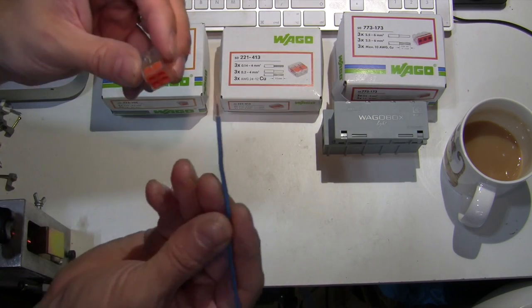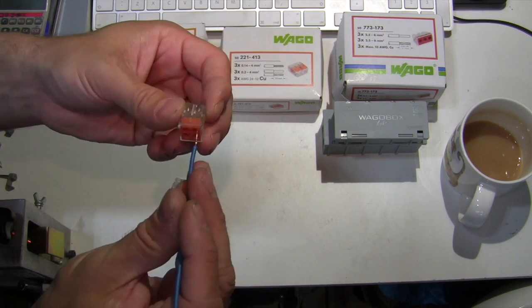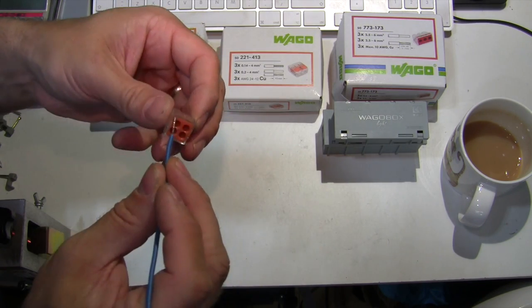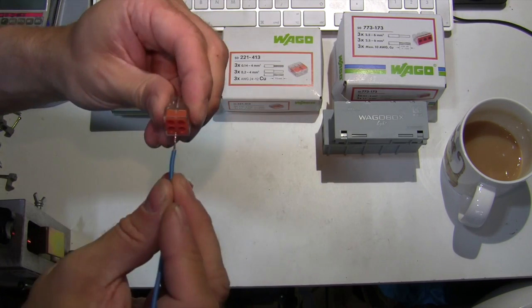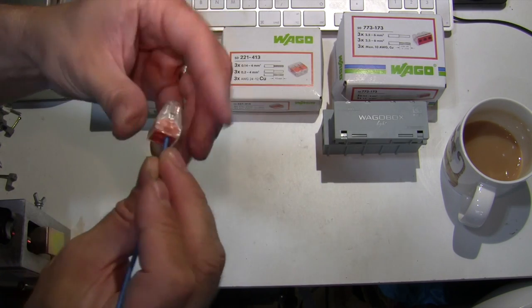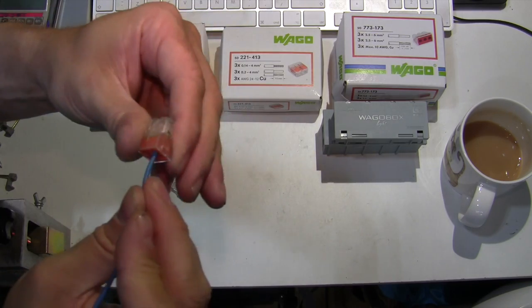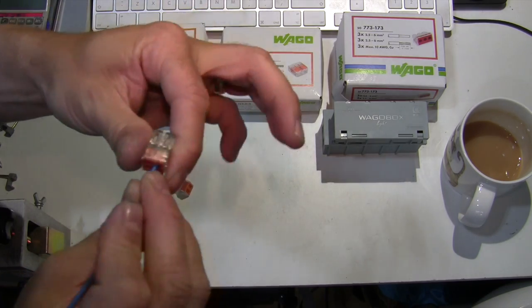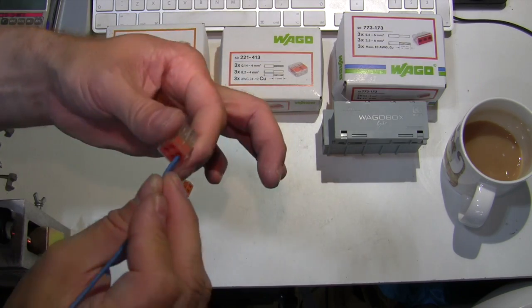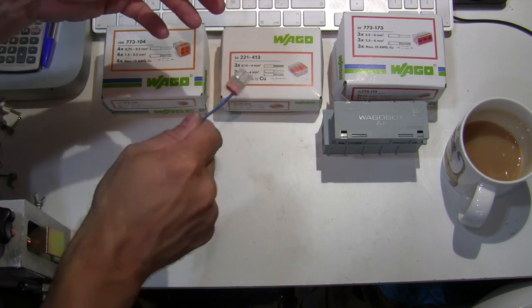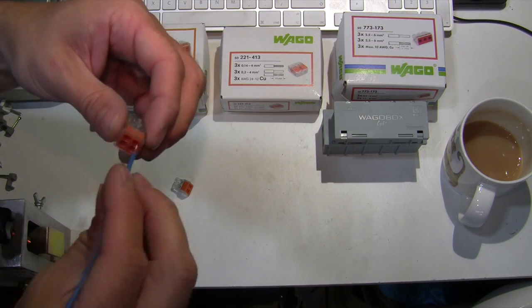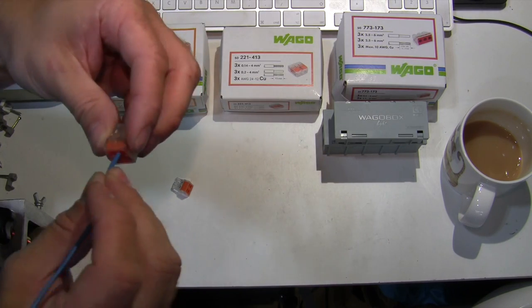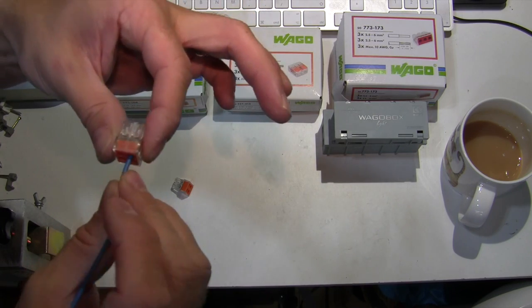But, and I've got a bit of 1mm cable here because it was a 1mm lighting circuit, it seems to be gripping on some of the holes. But look at this one. Not this one. That one. That is just not gripping at all. That is super loose. In fact, I could probably shake that off, although I fear it may go into my cup of tea if I do that. And it's a very hot day and I'm quite desperate to drink that.